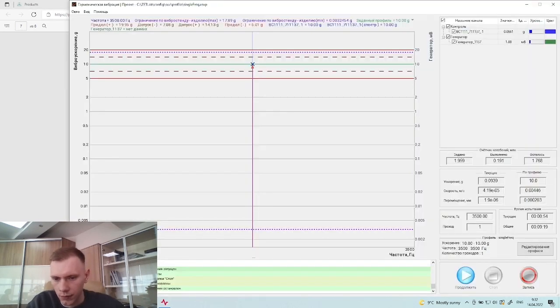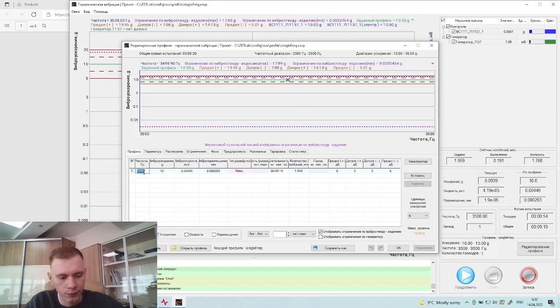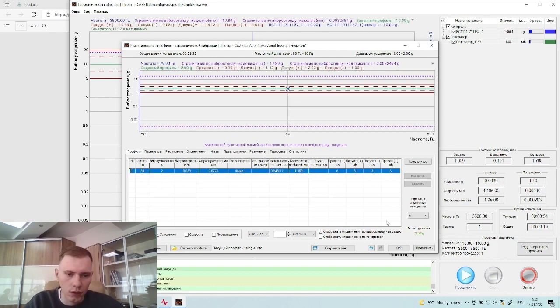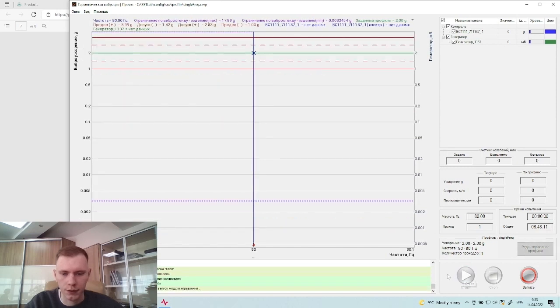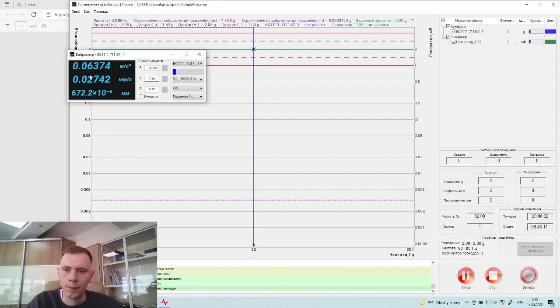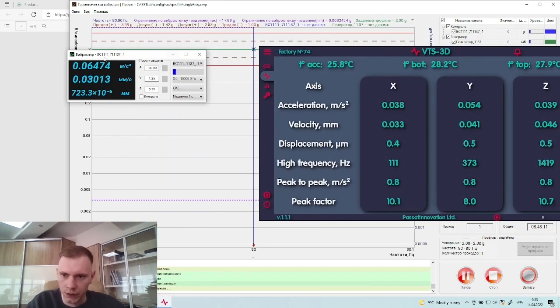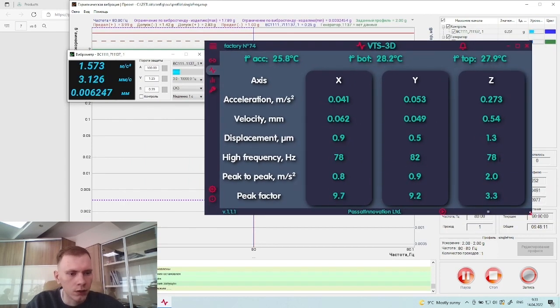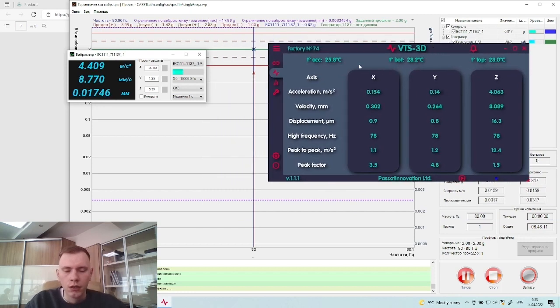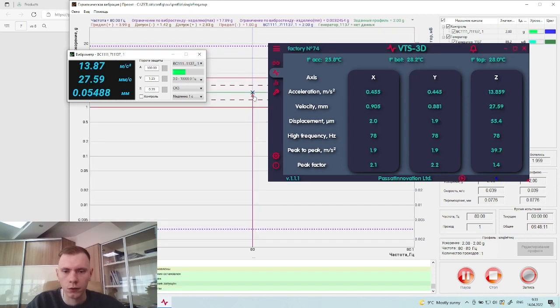Okay. So let's start from 80 Hz. I will put 2G. Okay, start. So in this window we have measurements from our feedback sensor BC111, and here the measurements of our sensor. Okay, so let's compare the values of our sensor to the feedback sensor. As we can see, at the calibration level there are no filters applied on this frequency, so we are getting the values as they are, and you can see that the values are almost the same compared to the feedback sensor.